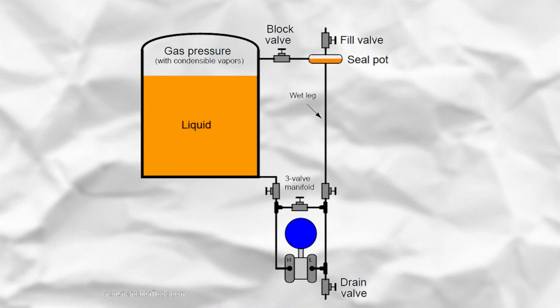In some applications where the vapor of fluid might accumulate on top of the tank, a steam trap or seal pot is mandatory to install. Otherwise, the vapor would enter the upper leg and become condensed and make a pressure column, which leads to error in the instrument. On this occasion only, the upper leg would be filled with water or glycol. Therefore, this leg is known as a wet leg.